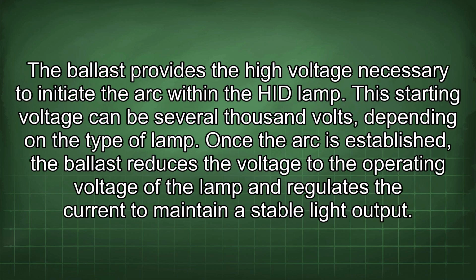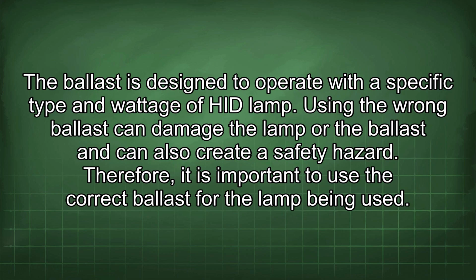The ballast provides the high voltage necessary to initiate the arc within the HID lamp. This starting voltage can be several thousand volts, depending on the type of lamp. Once the arc is established, the ballast reduces the voltage to the operating voltage of the lamp and regulates the current to maintain a stable light output. The ballast is designed to operate with a specific type and wattage of HID lamp. Using the wrong ballast can damage the lamp or the ballast and can also create a safety hazard. Therefore, it is important to use the correct ballast for the lamp being used.